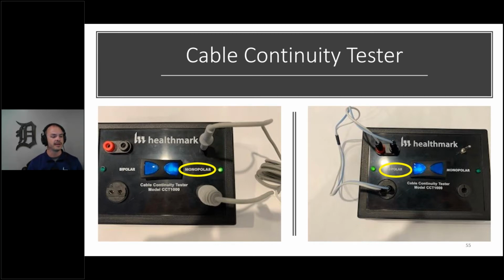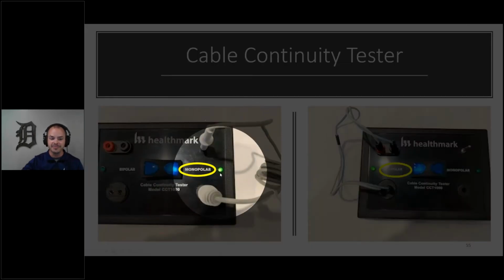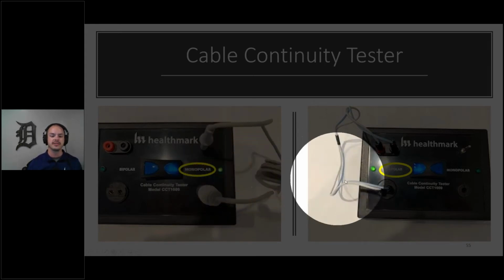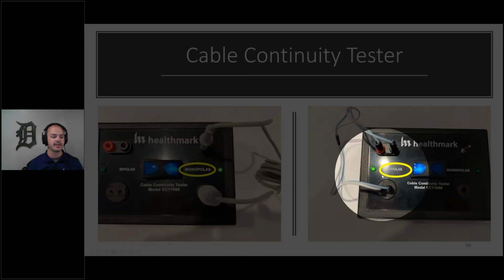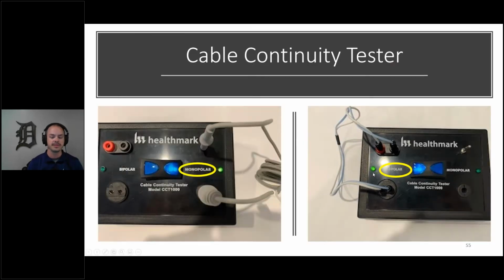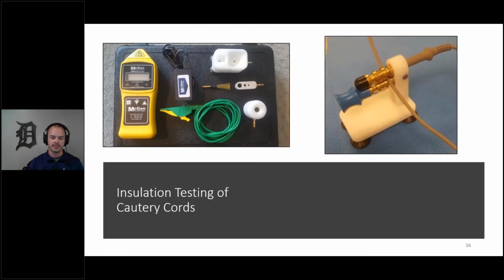We have a continuity tester here. Basically, this shows that the conductive material on the inside of your cord is working. That's the monopolar side, and that green light means it's a good circuit. That's the bipolar side, so we can test both types of cords, making sure the conductive material inside is intact and isn't going to lead to arcing or other problems. But the other component is insulation.